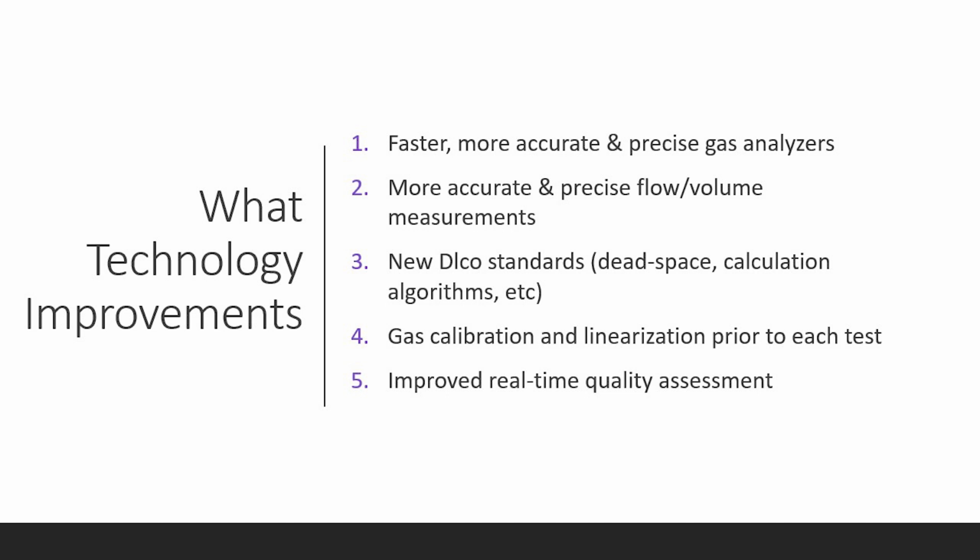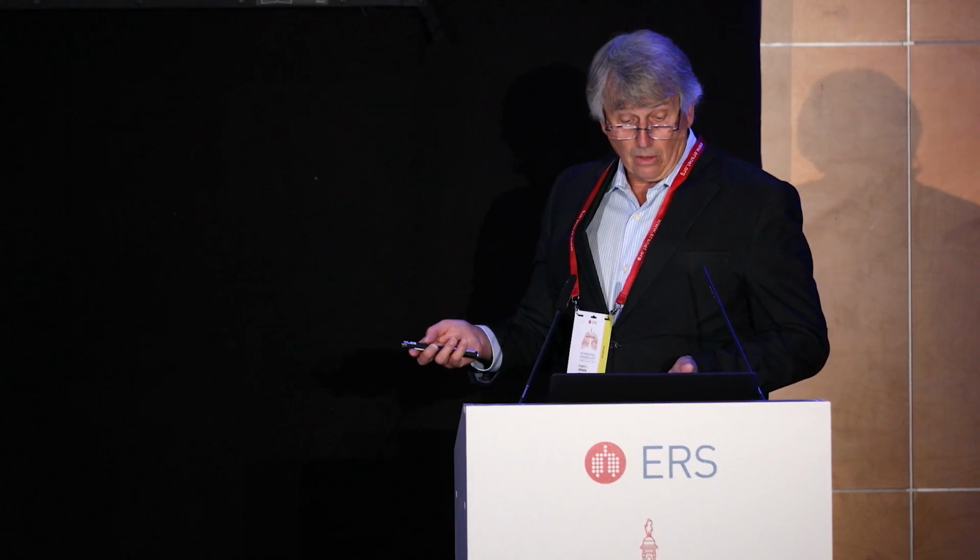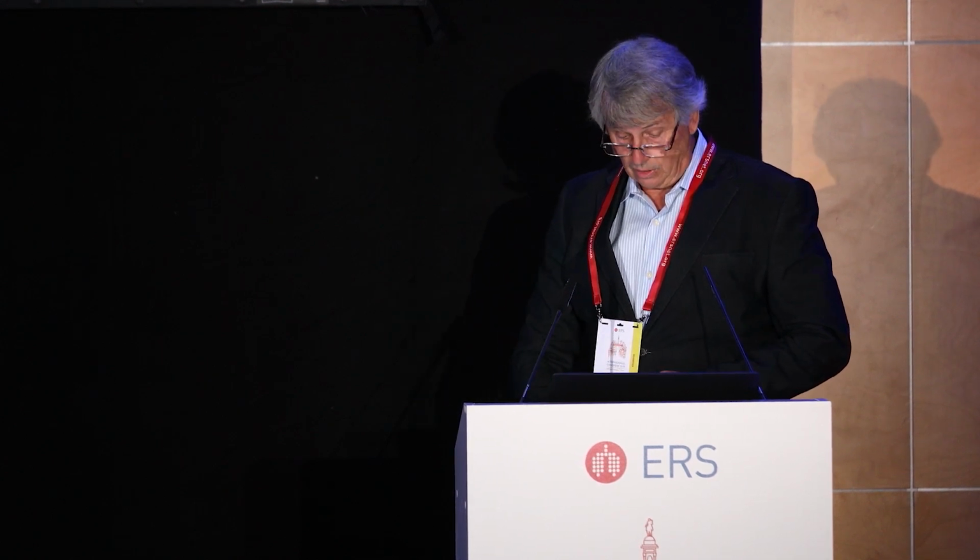Gas calibration and linearization prior to each test is now deployed, and an improved real-time quality assessment. That's where the algorithms underneath say, this is actually sort of meeting the new standards. This is a good test. This is not meeting the standards. It guides the technician. So in the end, it all helps improve the accuracy and precision of the devices that are coming onto the market today.